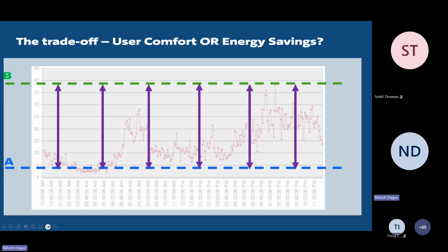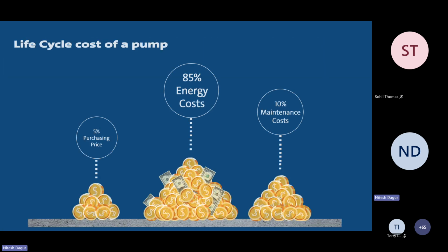So all of this talks about basically the operation of the pump that is needed in the building. And this is how the life cycle cost of the pump looks based on how we have selected it, or any pump rather. So only 5% of the cost goes into the purchasing price of the pump. So that is our capital expenditure when you're thinking of buying a pump or investing in a pump in any commercial application. 10% are the maintenance costs, and life cycle can be anywhere between 10 to 15 years or even 20 years at times. 85% of all that money goes into the energy costs that the pump is consuming.